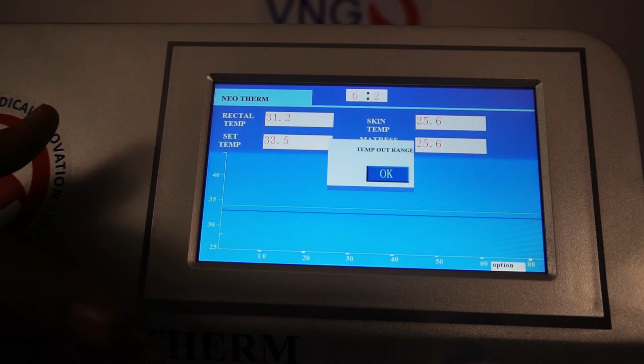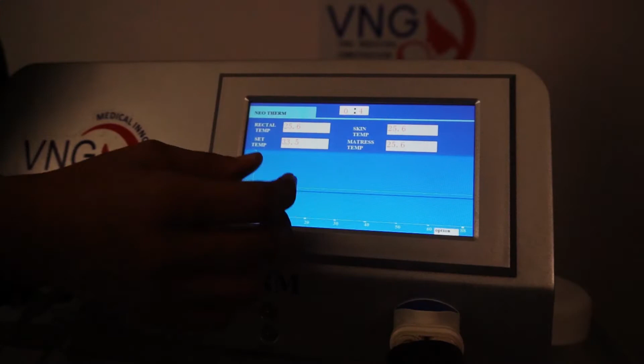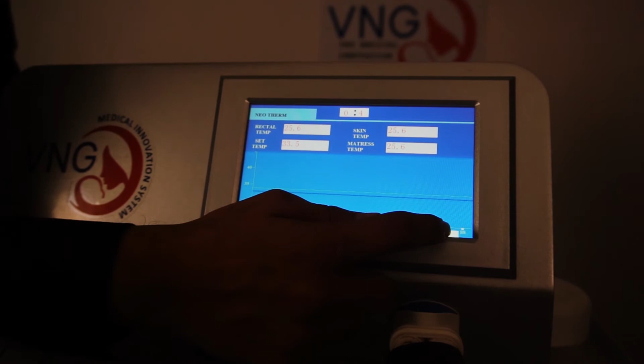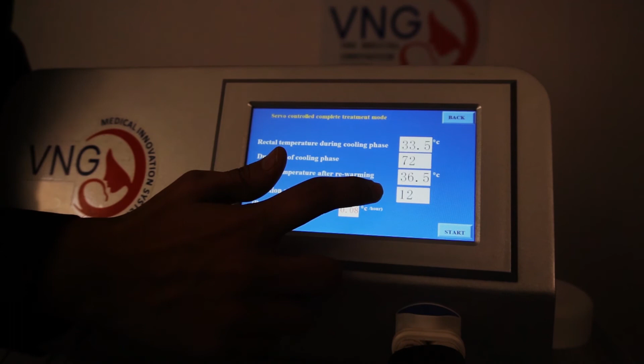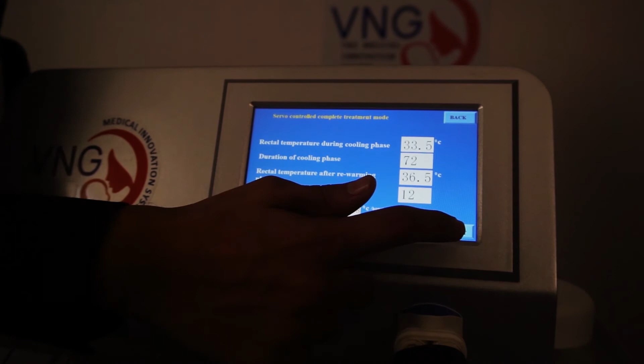When the temperature of the baby either exceeds by 1 degree Celsius or recedes by 1 degree Celsius, the machine will warn you by giving an alarm. In this case, you need to check for the safety precautions of the baby. Kindly check your NICU temperature compliance or the rectal temperature of the baby. During the operation, whenever you want to change the settings, you may click on the option button and then the option during operation. Change the settings, and this will allow you to change any kind of parameters you have input in the machine before the therapy.